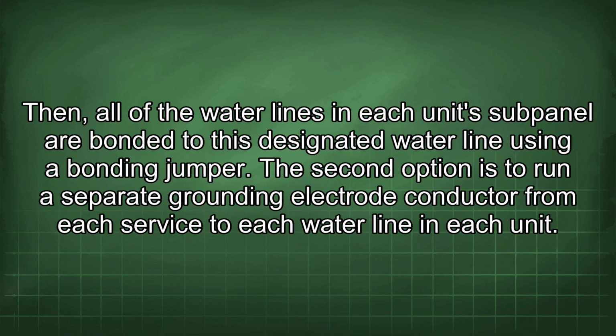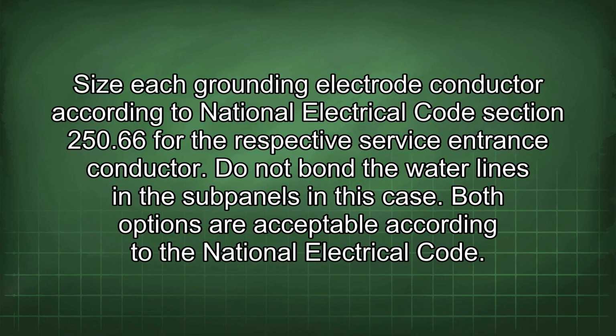jumper. The second option is to run a separate grounding electrode conductor from each service to each water line in each unit. Size each grounding electrode conductor according to National Electrical Code Section 250.66 for the respective service entrance conductor. Do not bond the water lines in the subpanels in this case. Both options are acceptable according to the National Electrical Code.